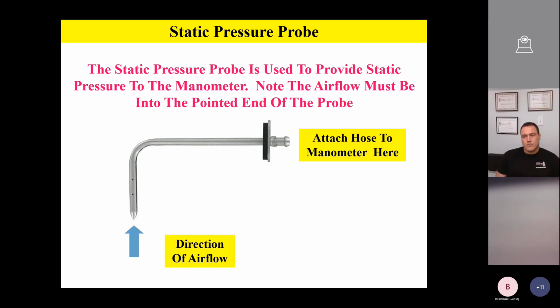And so good practice is you put this in, and you also notice that on the static pressure probe, it has a magnetic base to it. So you can snap it on to a metal ductwork if you have metal ductwork. If not, you're just going to have to hold it. If it's like duct board or flex duct, you'll have to just hold it into the airstream. But you always want to make sure that pointy end, that you'll see the 90 degrees there, is going into the direction of airflow. That's really important as you take a look at that graphic.